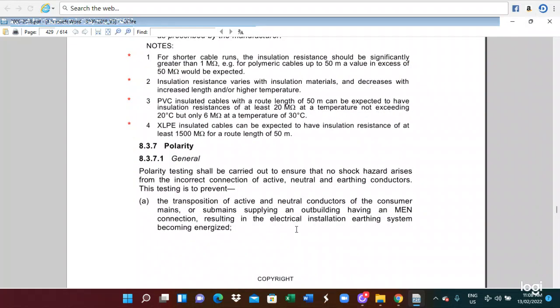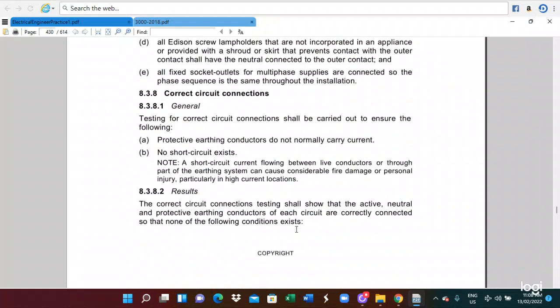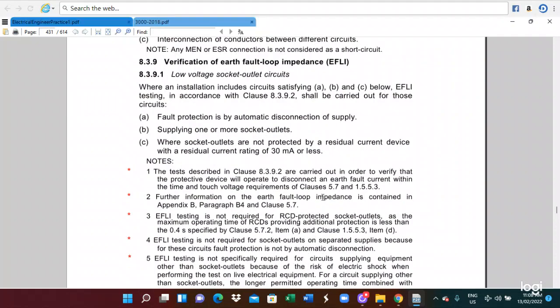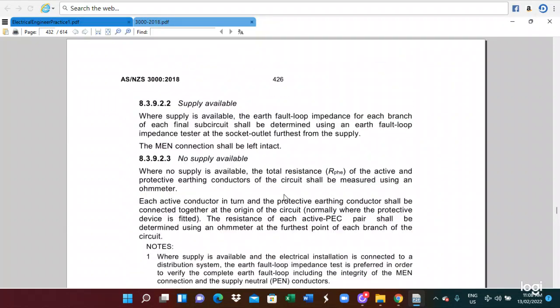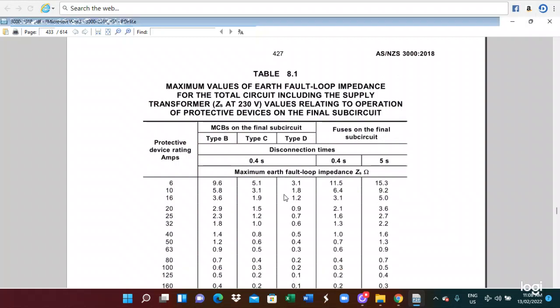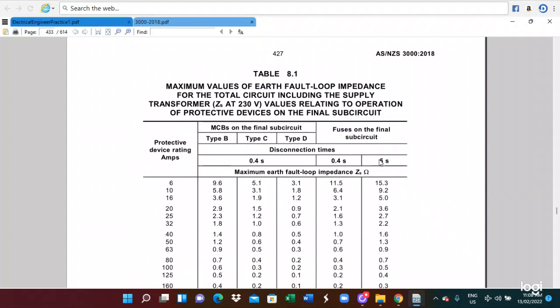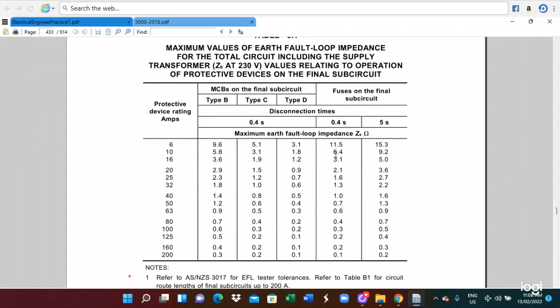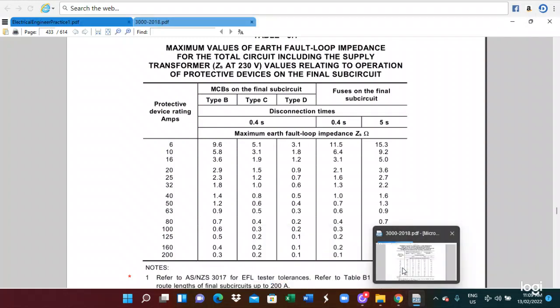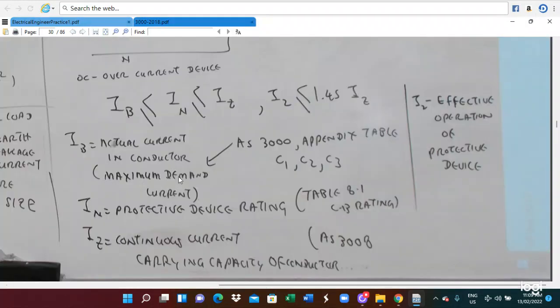Circuit breaker rating is in Table 8.1. So you look at Table 8.1, there will be the type B, type C, and type D circuit breaker, and also the final sub-circuit. Depending on the impedance and on the circuit type of the protected equipment, you can calculate the protective device rating. So that protective device rating is this one. This is for the IN.